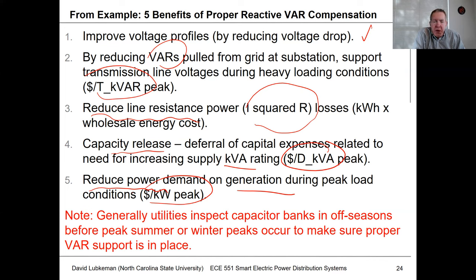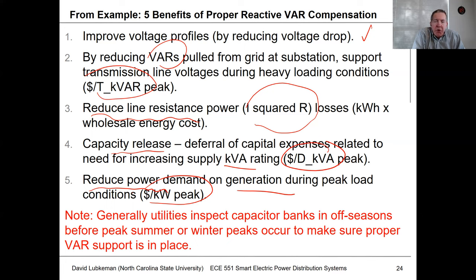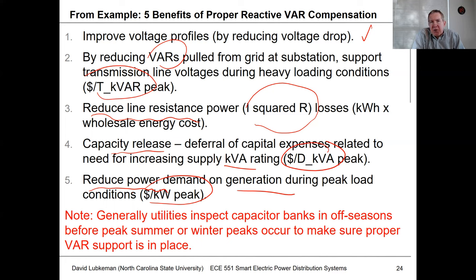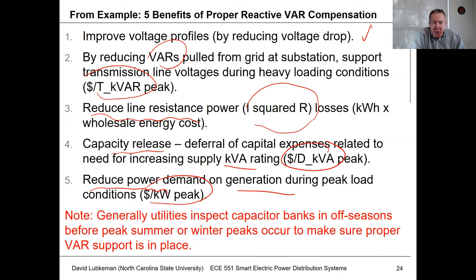The benefit of capacitors is so high that utilities typically do field inspections before peak conditions occur — whether summer or winter peaks — to make sure all capacitor banks are working correctly, since fuses may blow due to harmonics or other causes. Having all capacitor banks in correct operational form before hitting peak conditions is a critical operational practice.